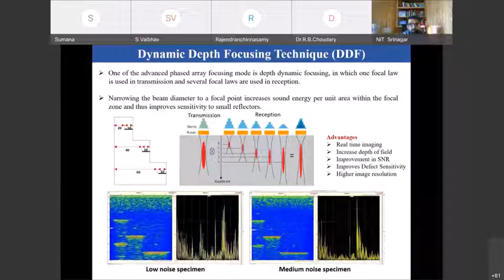Using a 32-element aperture, during the transmission we focused at nearly 40 mm depth, and on the reception side we set the initial and final position of the focal point from 10 to 75 mm depth. So we were able to get, in both low noise and medium noise titanium calibration blocks, all the defect signals with high sensitivity. This is the defect signal from 20, 40, and 60 mm depth, and these are the corresponding step backward echoes from these steps. And these are from the multiple reflections from the first flat bottom holes and from the first step backward echoes. So this shows clearly that DDF gives better sensitivity and SNR compared to conventional ultrasonic testing.